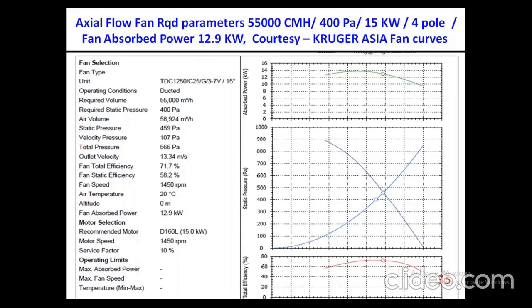Why do the axial flow fans need to be resized? Because it is all meant for peak summer conditions. It is all designed for the maximum conditions. But throughout the year, the summer condition is not there. So definitely the axial flow fans also need the VFD, and that has to be operated to the best efficiency point of the fan performance curve. In fact, the VFD is a facilitator for the given blower to achieve the best efficiency point for the fan performance. This is what we have to visualize: the VFD's flexibility to achieve this best efficiency point.